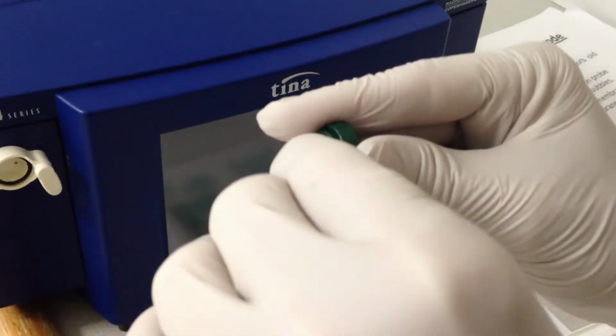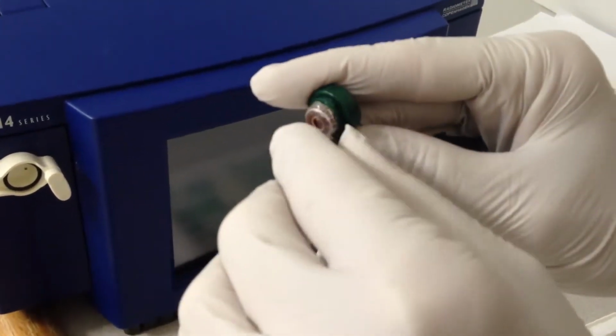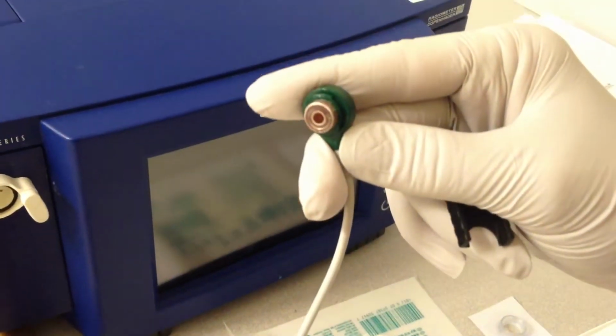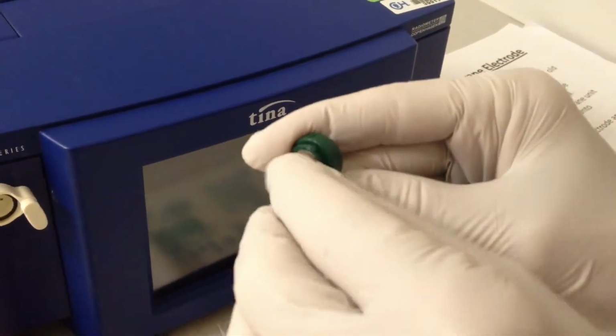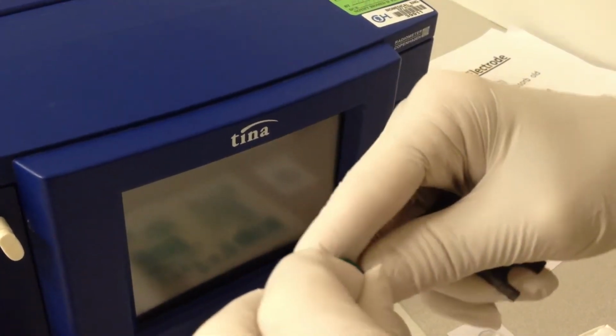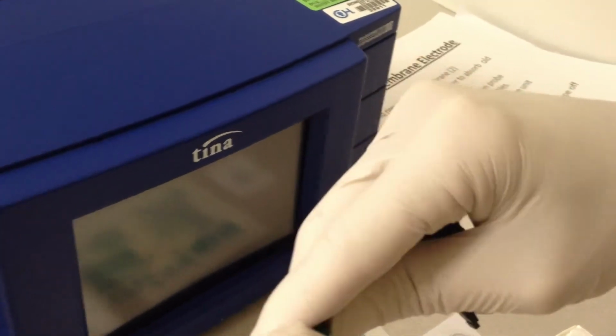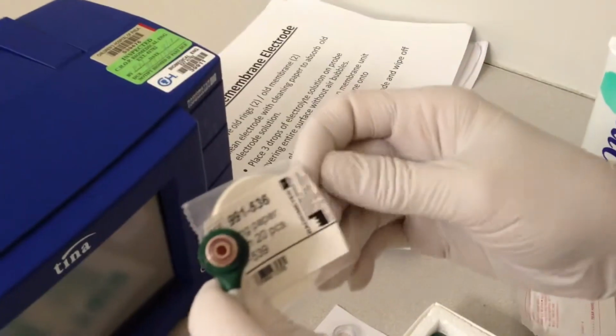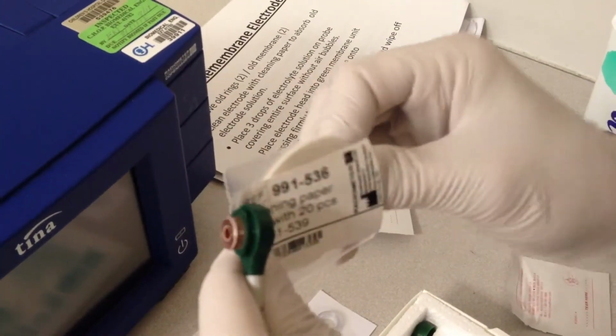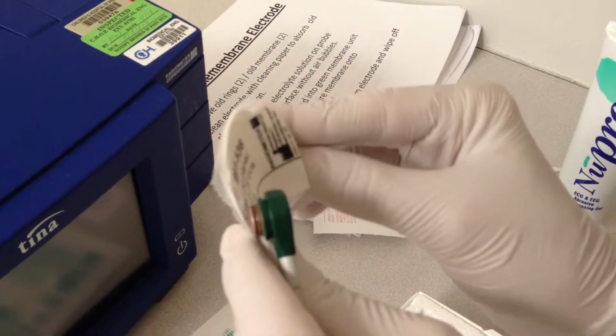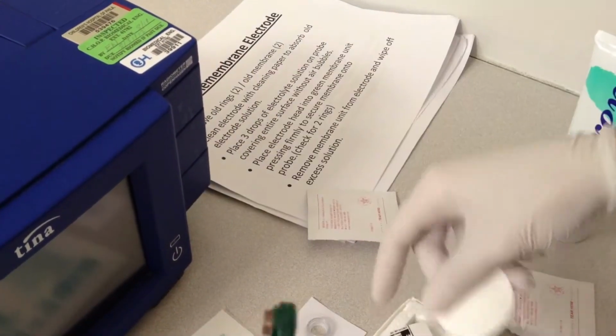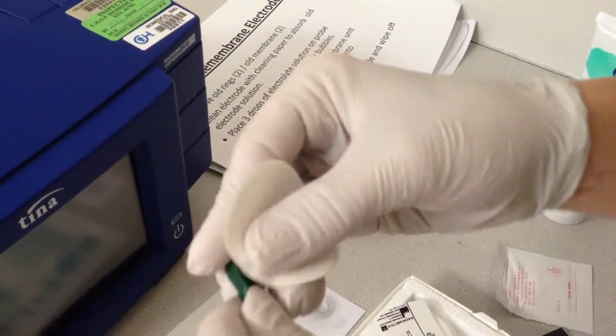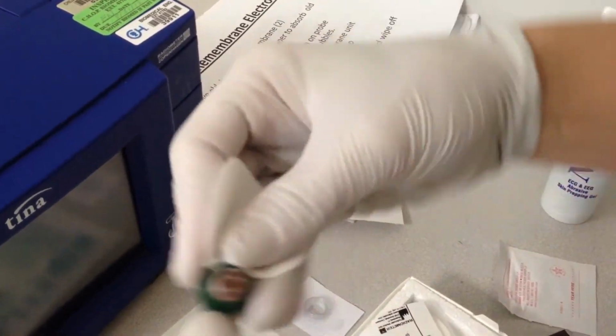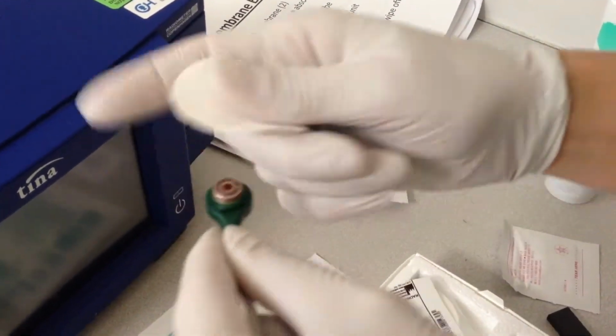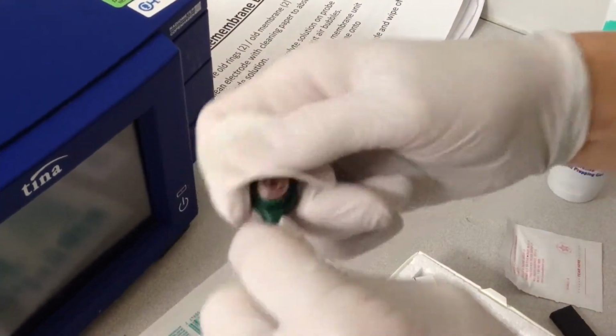And then you want to make sure that you get all of the layers from the electrode gel before putting a new membrane on. Then you're going to want to take your cleaning paper and clean off the remaining electrode gel from the prior probe. You want to really just get a good wipe. Go around the surface until it's nice and dried.